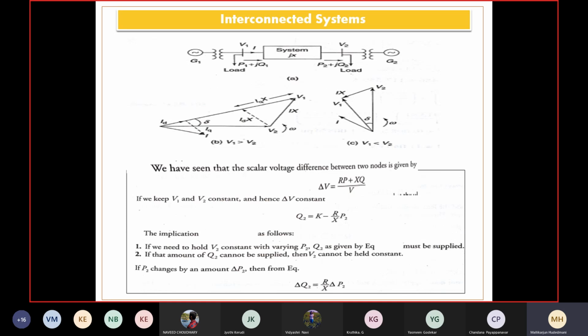So it is not only the Q requirement that causes the voltage change. Q requirement will change because of P requirement also. And Q requirement will keep an eye on V. If we are not able to supply Q properly, V you cannot maintain. If we cannot maintain V properly, P we cannot maintain constant, because we know between two buses, active power delivery P12 is V1 V2 divided by X sin delta 12. There comes a voltage. If Q cannot be maintained, that is because of V. If V cannot be maintained, P gets affected. If P gets affected, Q gets affected in this way. So there is a triangular connectivity between reactive power and voltage, and voltage and active power.